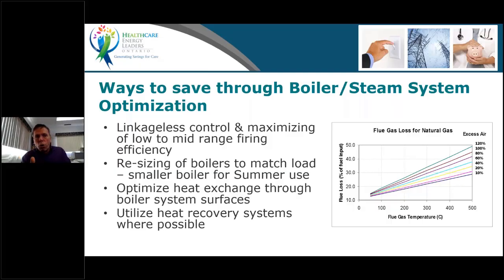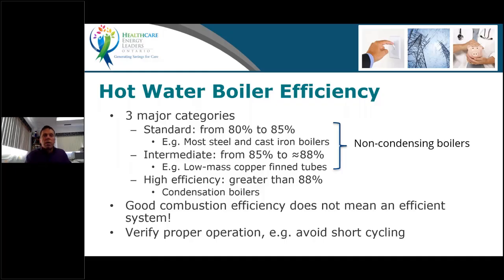Another place you're going to look at in a boiler plant, like I said, is heat recovery. There's many possibilities for heat recovery, and you have to look through the different possibilities. Usually you need a specialist with you to identify where heat recovery is possible. A few things you also need to be familiar with when you talk about boilers. Here we're talking about, let's say, hot water boilers. You've got the standard efficiency, which is not hard numbers, but the minimum is 80%. That's the regulated minimum for gas boilers. A new one cannot be bought below 80%, unless it's a used one. So 80 to 85% would be considered standard efficiency.